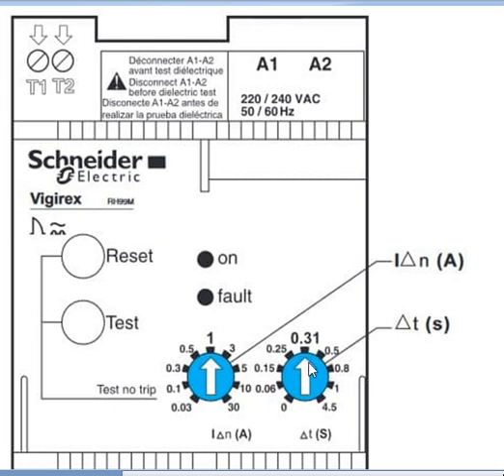Next friends, this is the time. Normally if there is any earth leakage, the circuit must be disconnected in milliseconds from the main source to protect human life. In earth leakage, if anyone touches the machine and there is some leakage current flowing in the circuit, it is harmful for the human being. So we have to trip the machine as soon as possible, within milliseconds. So friends, the range is from 0 to 4.5 seconds. It's up to you how much you are going to set.